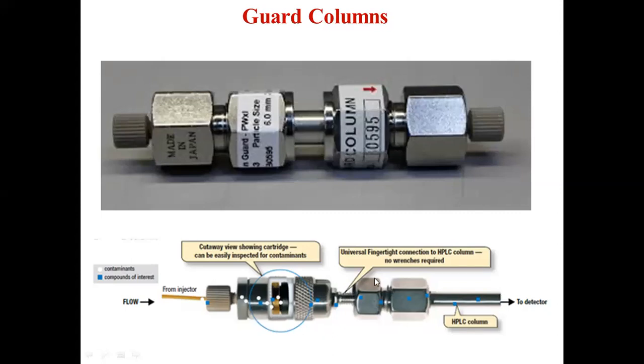So this guard column will be present before the analytical column and after the sample injection port. The guard column of this type will be present before the analytical column and after the injection port. Once the sample is introduced, any impurities present in the sample are going to be bound to the stationary phase of the guard column, and the particulate matter is also going to be removed. If there are any unwanted species present in the mobile phase, they are going to stay in the guard column, and the samples with the respective suitable number of solutes are going to move towards the analytical column. So this is the HPLC column or analytical column where the exact separation is going to take place.